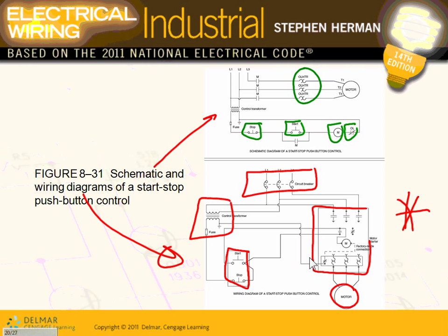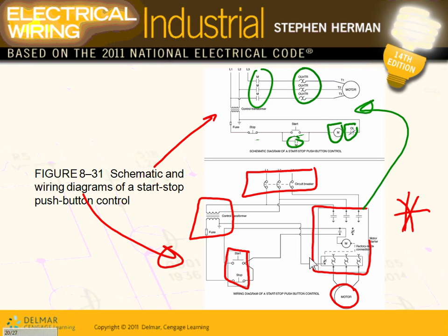Can you see that? All these highlighted items are in one box — the coils, the overloads, and these contacts are in one box right here. The schematics will help you understand how the system works. The wiring diagram will help you actually go wire it — give it to an electrician, and they can do point-to-point wiring between different equipments. Can you guys see the difference between how components appear scattered in a schematic versus grouped in a wiring diagram?